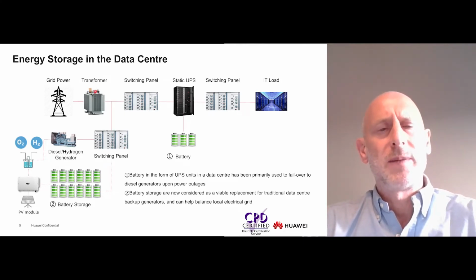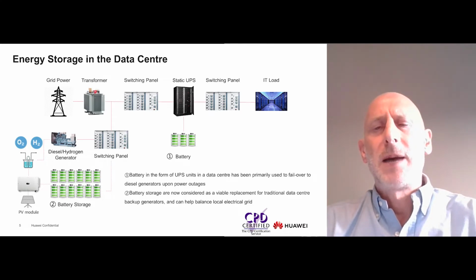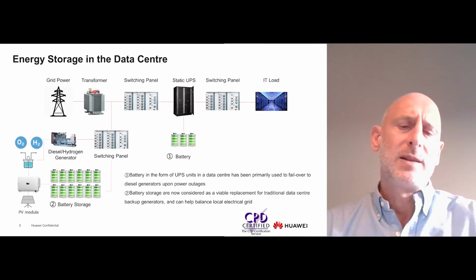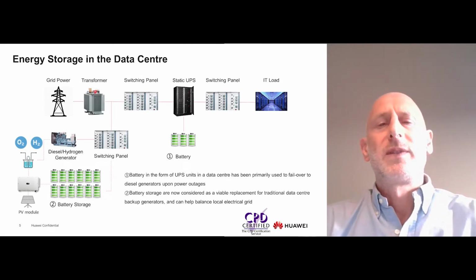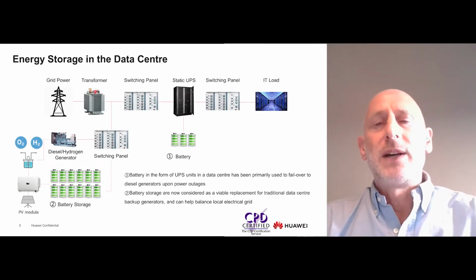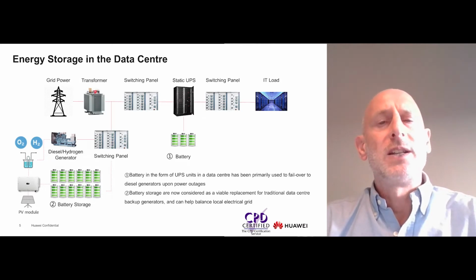In the event of a grid outage, an automatic mechanism will seamlessly switch the facility from grid power to diesel power. An intermediate emergency power backup is provided by a battery-operated UPS system for the IT load. Not all direct backup power is available for compressor or chiller units, so the diesel backup power needs to start and ramp up as fast as possible to take over the entire load.